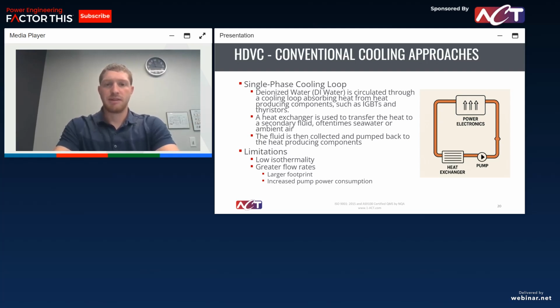Once again, in many cases, especially with lower power densities, you're going to have a lot of success with the single phase cooling loop. Limitations though, low isothermality. So what you're going to have is a lot of your power electronics are going to do more thermal cycling, which is going to reduce the lifespan of those components.